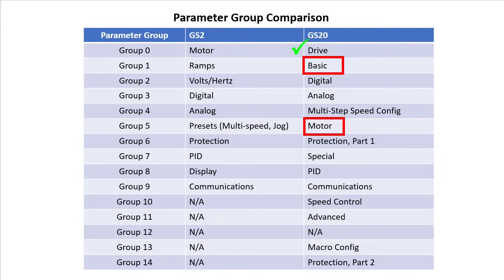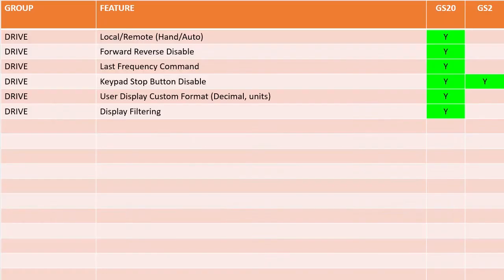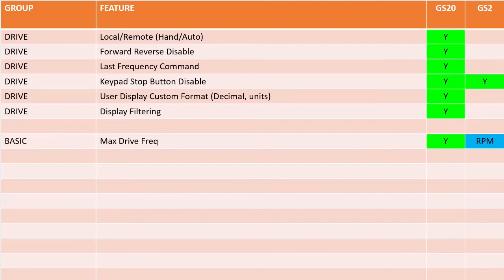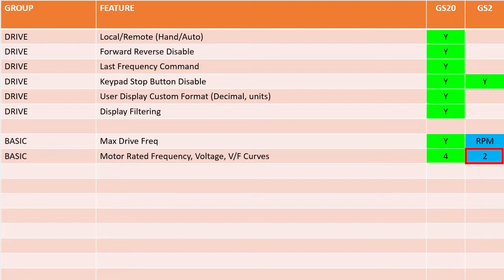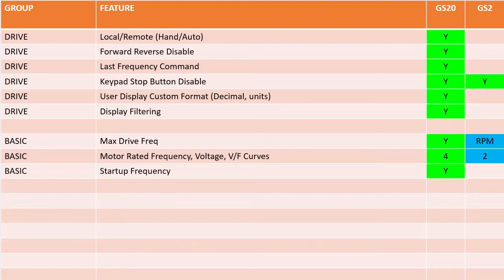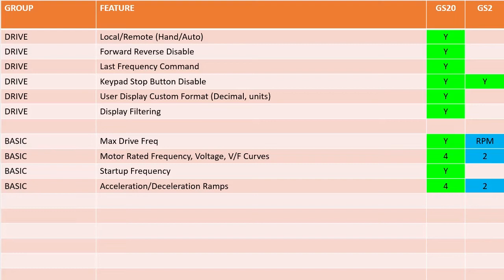The basic and motor groups are all about the motors, so let's do those two next. On the GS20 you set the max drive frequency the motor can handle; on the GS2 you set the max motor RPMs — that's a subtle difference you need to be aware of. Both drives have the usual motor rated frequency, voltage and volts-hertz curves, but the GS20 supports up to four different motors while the GS2 only handles two. The GS20 also allows you to specify a startup frequency so you don't have to manually enter a speed after a power cycle when using the keypad or comms for frequency control. Both drive families have acceleration and deceleration times, but the GS20 has four to select from while the GS2 only has two.